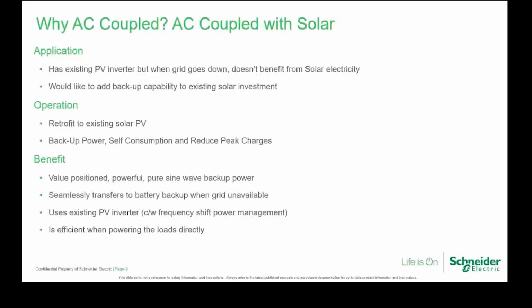Why AC couple? Basically, the applications are where you have an existing PV inverter, but when the grid goes down, it doesn't benefit from solar electricity. You want to make sure that even if the grid has gone down, the PV inverter still runs and provides energy back to the loads. You can also provide a backup capability to an existing solar investment. On the operation side, you can retrofit to existing solar PV if the existing PV inverter is compatible with the XW Plus or XW Pro. You can then have backup power, self-consumption, and you can also reduce your peak charges.